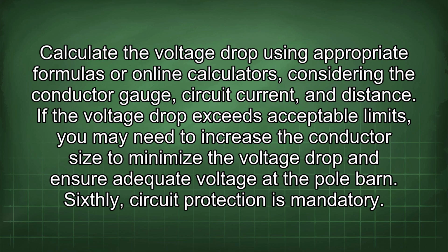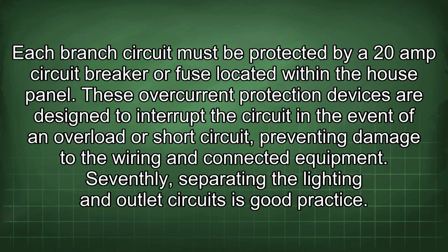Sixthly, circuit protection is mandatory. Each branch circuit must be protected by a 20-amp circuit breaker or fuse located within the house panel. These overcurrent protection devices are designed to interrupt the circuit in the event of an overload or short circuit, preventing damage to the wiring and connected equipment.